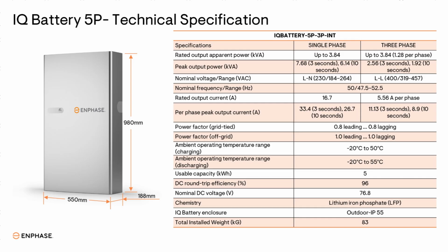For peak output power, these batteries can withstand twice their capacity for 3 seconds and 1.5 times for 10 seconds, so that your heavy loads, your motor loads, like your kitchen juicer mixer or grinder, your 1 HP or 1.5 HP water pump, or your AC or your refrigerator, means any equipment which has a motor or which takes a jerk load, or you can say the inrush current from the grid for a second at startup, also known as the startup current.